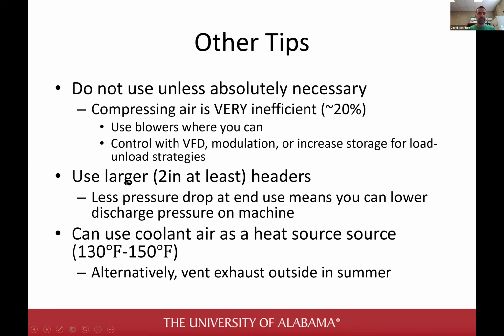Control with VFD, yes. Another thing is we didn't get into this, again, it's a long subject, but use larger headers where you can. The smaller the pipes that you have, the more pressure drop is going to go around. You're going to need more pressure drop to get through those pipes. So if you can get larger headers, 2 inches at least, I would recommend. 4 inches if you have a large facility with a lot of compressed air. You're not going to have a huge pressure drop to the other end of your plant, and that ends up being huge.